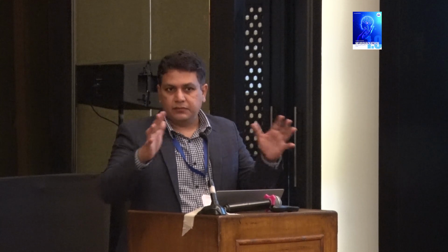So this is the typical construction of the Phenom catheters. Not only Phenom Plus, but all of the other Phenom family catheters. And you will notice that this is the standard way of constructing a catheter, even for competitive catheters. You have three zones. You have the proximal zone, which is typically constructed from braids. We use braids because it gives you that support and pushability to be able to park it on the proximal section. Then you have a small transition zone going from the braid to the coil. And then the distal segment is where you need it really soft, because that's the part that goes through the severe tortuosity. So it's typically made from coils so that it's highly kink resistant.